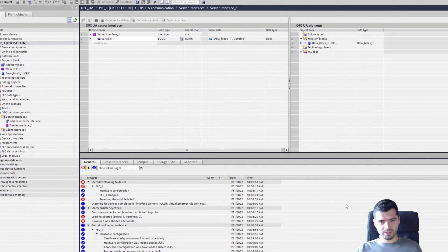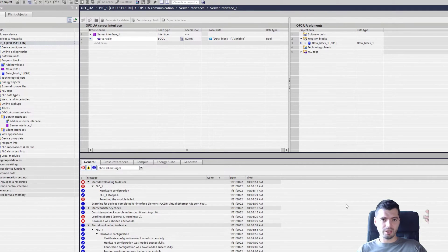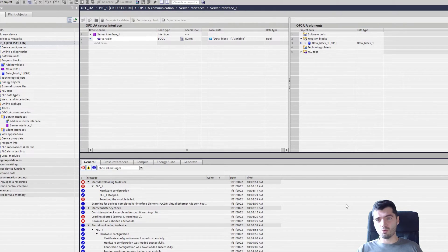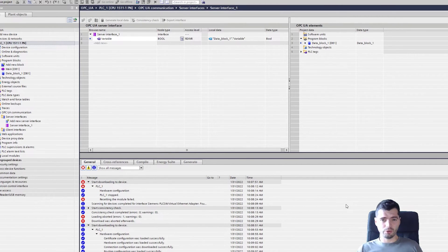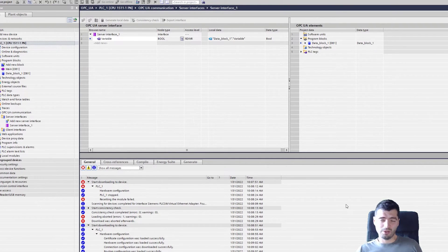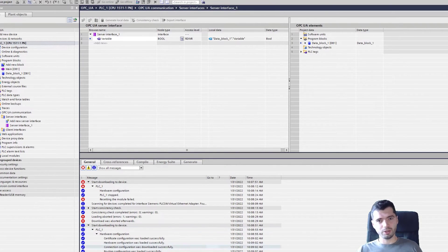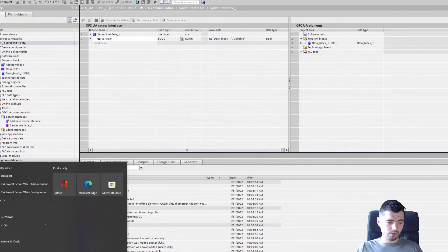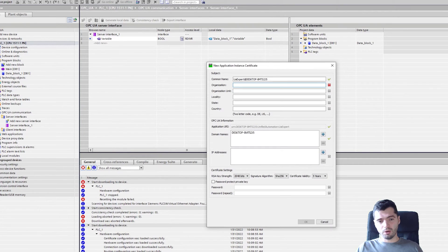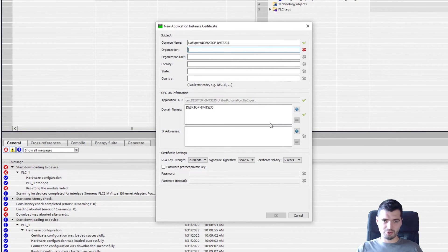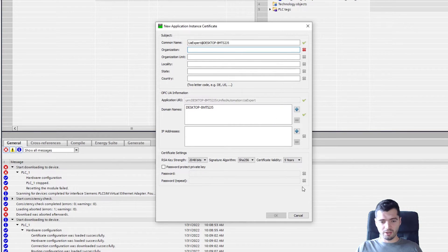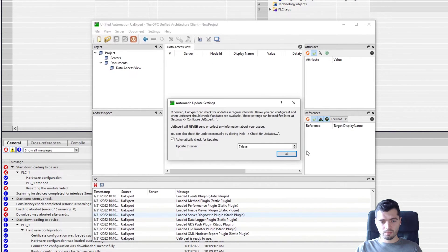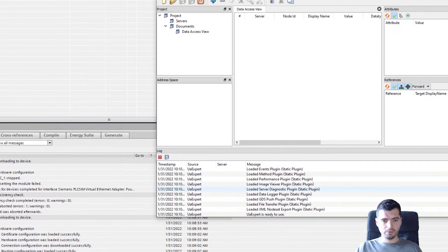How can I test this? Maybe you have a client software of some kind, a high level system that should be subscribing to this data, grabbing it over OPC UA and it doesn't work. So how would you go about troubleshooting? For me, my favorite troubleshooting tool is UA Expert. It's a free OPC UA client. I use it quite often to just make sure that everything works fine and I can actually access my OPC UA server. So I have UA Expert installed, but if you just Google it, you will go onto these guys' website. They have some products that they sell, but if you register on the website, you can actually download the UA Expert client free of charge.